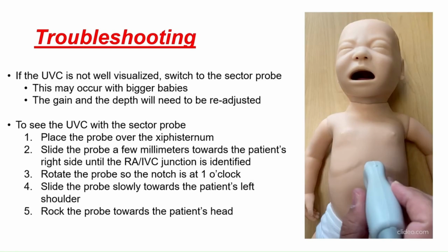The next few slides will go over troubleshooting in case visualization of the UVC catheter with the linear probe is not feasible. Switch to the sector probe. This may be needed with bigger babies. The gain and the depth will need to be readjusted as well.